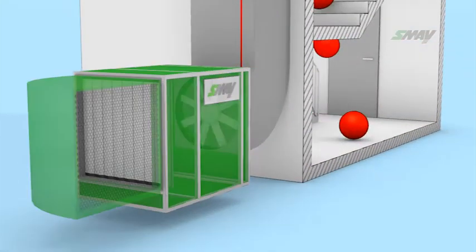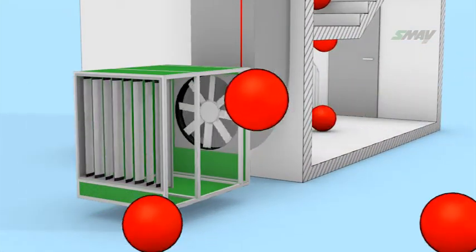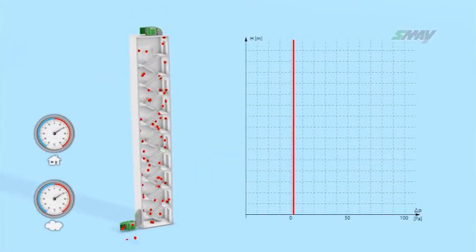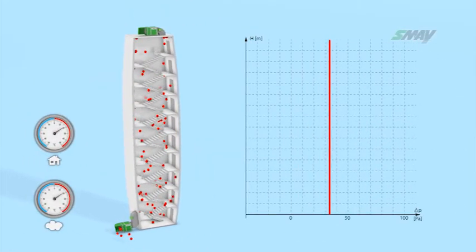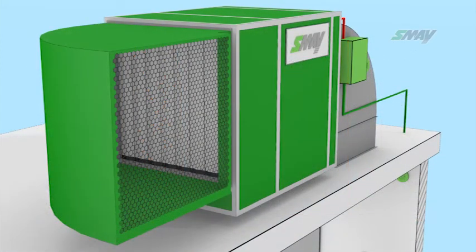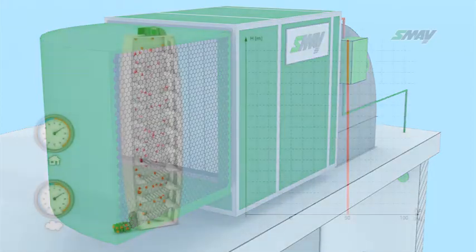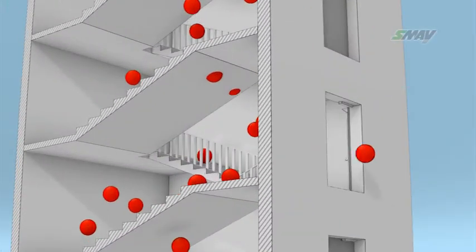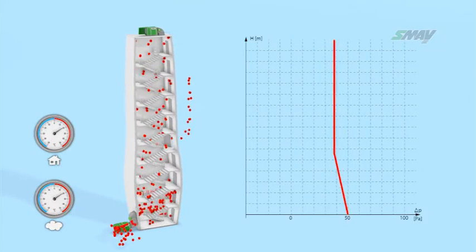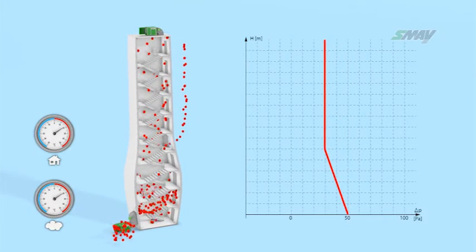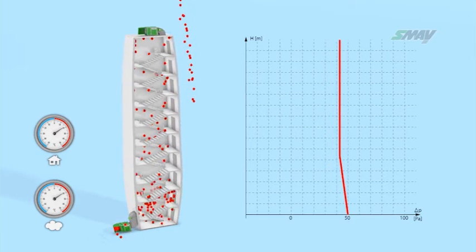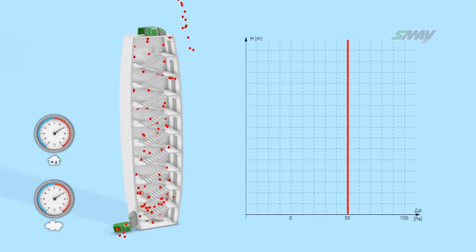If there is no temperature difference between the internal and external air, then one of the fans supplies a small amount of air to the stairwell needed for the required 50 pascal, and the other one is cut off by a closed regulatory damper. If doors are opened and pressure inside the stairwell drops, then the fan will increase the air supply rate. Once the doors are shut, the system returns to observing the pressure criterion and supplies an amount of air needed to counteract the stack effect and airflow resistance.